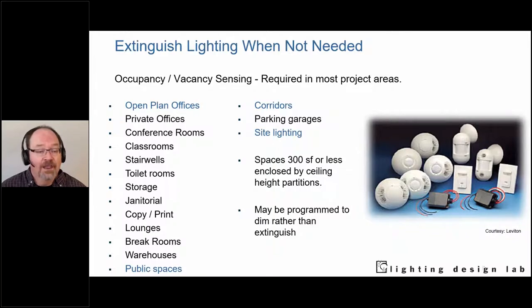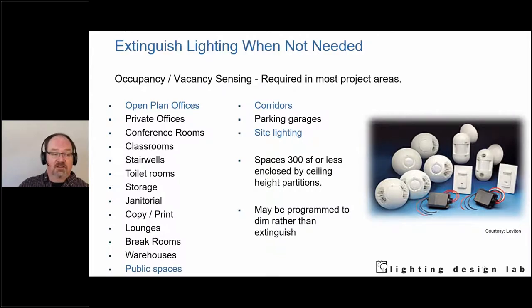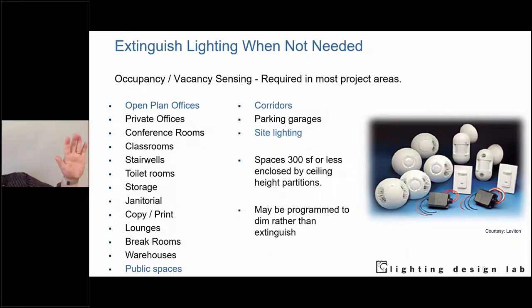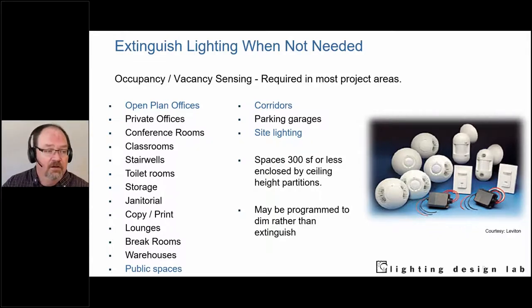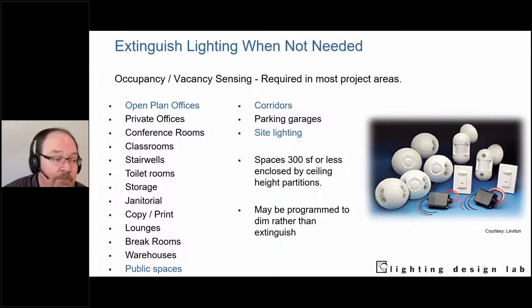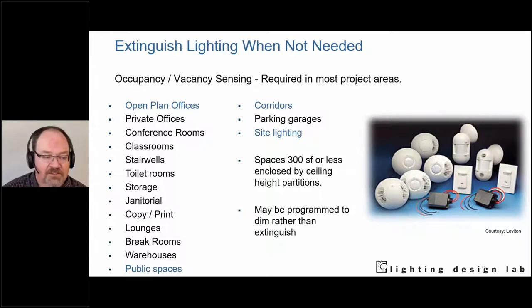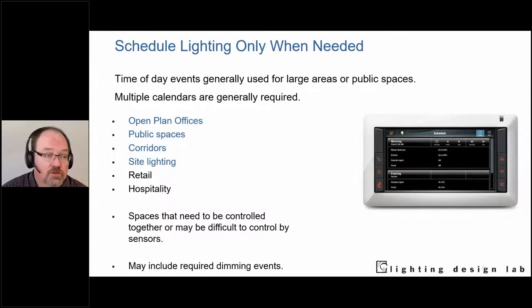The one place I'll tell you never to use lighting controls — an electrical or mechanical closet. If your hand is 10 inches from an energized bus bar, you don't want the lights going off. Use a toggle switch with a lockout there. Otherwise, use occupancy sensors and scheduling: schedule lights only when needed. Time-of-day scheduling is less common than it used to be — we've moved away from simple time clocks to using scheduling primarily for fine-tuning sensor behavior, except in lobbies, atria, or retail establishments.